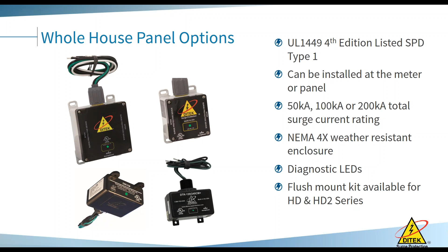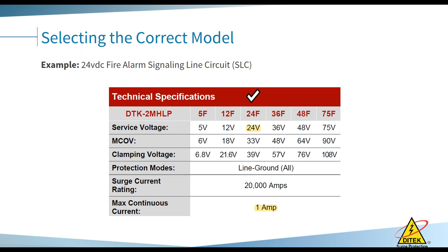When you're getting the low voltage, you want to select models. Sometimes people look at these charts and they think they're kind of overwhelming. It's pretty straightforward if you look at it this way. Technical specs, we talk about service voltage. Okay, in this case, what am I going to put on an SLC loop? Awesome, I want the 2MHLP. My service voltage is 24. Okay, 24F. If you look down, great, MCOV, clamping voltage, and maximum continuous current 1 amp. That's the perfect device for me.